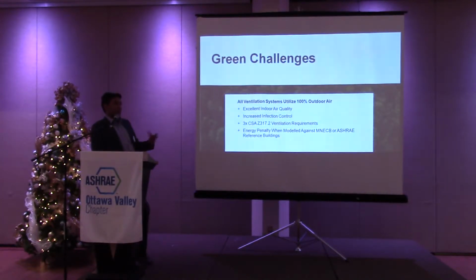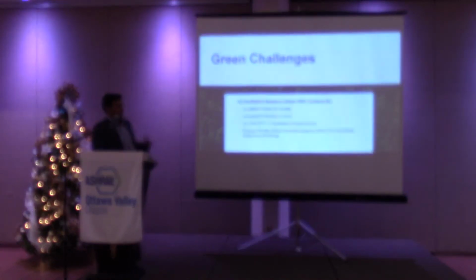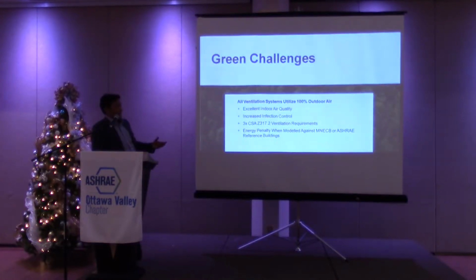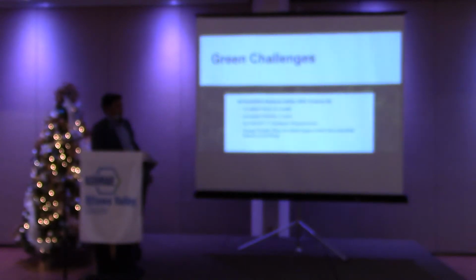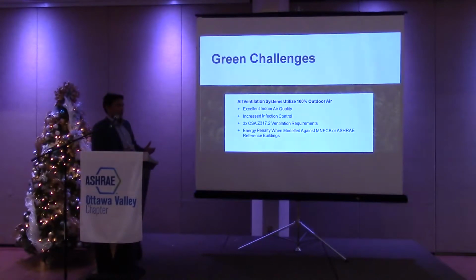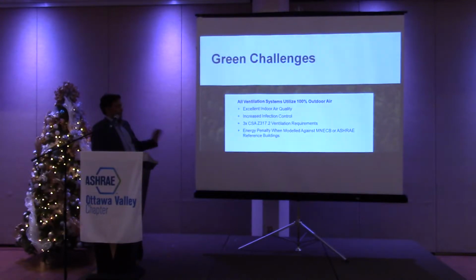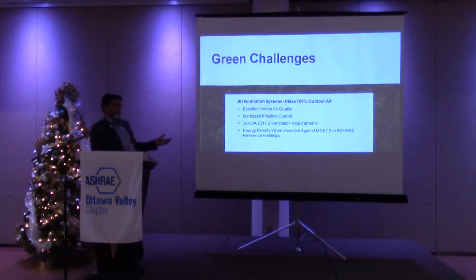One of the ways they did that was 80% of inpatient rooms are single patient rooms, right? So that's the new CSA standard, and they go in that direction. So they funded that, and that's to avoid cross-contamination between patients. But as we know, airborne infections are a real thing that happens, and there are many departments where people come through the hospital, and they're walking through the hospital, they might be contaminating people before they get to a point where they're being isolated. So it's not like you can eliminate airborne infections, but certainly when you go to 100% outside air, you help reduce it. The CSA standard that governs healthcare in Canada requires 33% outdoor air, roughly, in most departments and most areas, and so they're asking us to exceed that by 3 times.